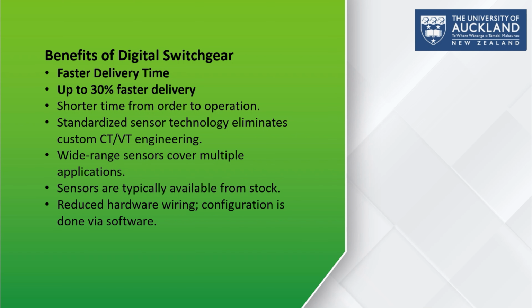So with digital switchgear, delivery can be up to 30% faster. This means a shorter time from ordering to actual operation, right? There are several reasons behind this improvement. First, sensor technology enables a one-size-fits-all approach, unlike traditional CTs and VTs that need more engineering customization. The second is that the sensors have a wider operating range, so the same sensors can be used for many different applications, reducing design and procurement delays. Third, these sensors are typically available in stock, eliminating long lead times. And the last is the hardware wiring. As the hardware wiring becomes minimal, most configuration can be handled through software, which speeds up installation and commissioning, right?